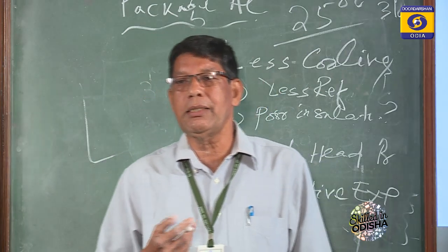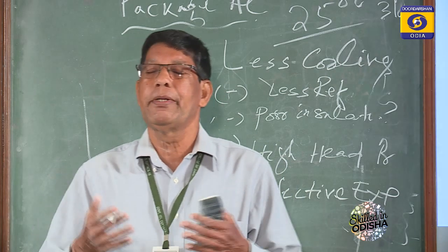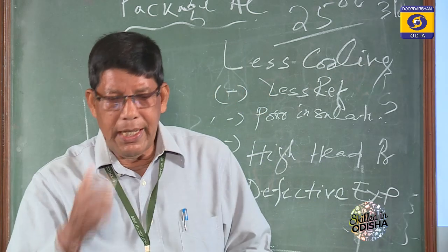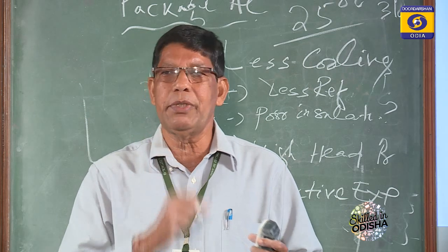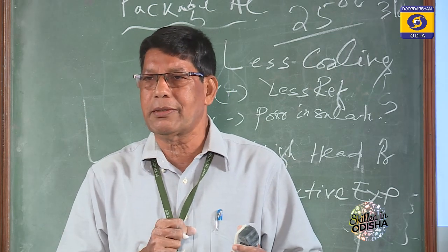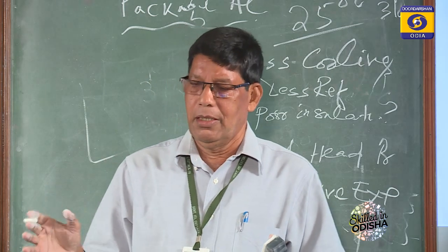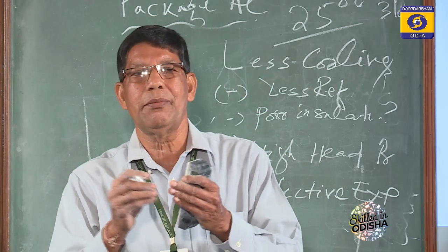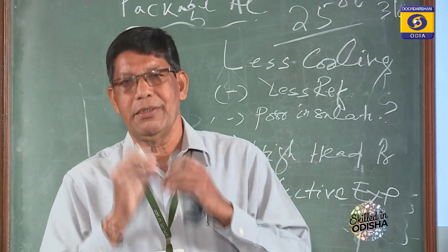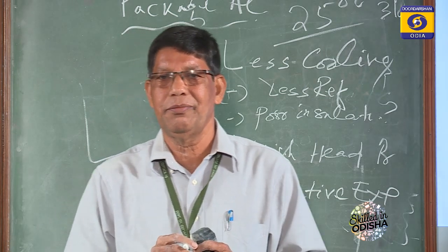Then another is a defective dryer. Suppose it is not absorbing the proper water particles and moisture present in the refrigerant. So there is the question of choking in the system.